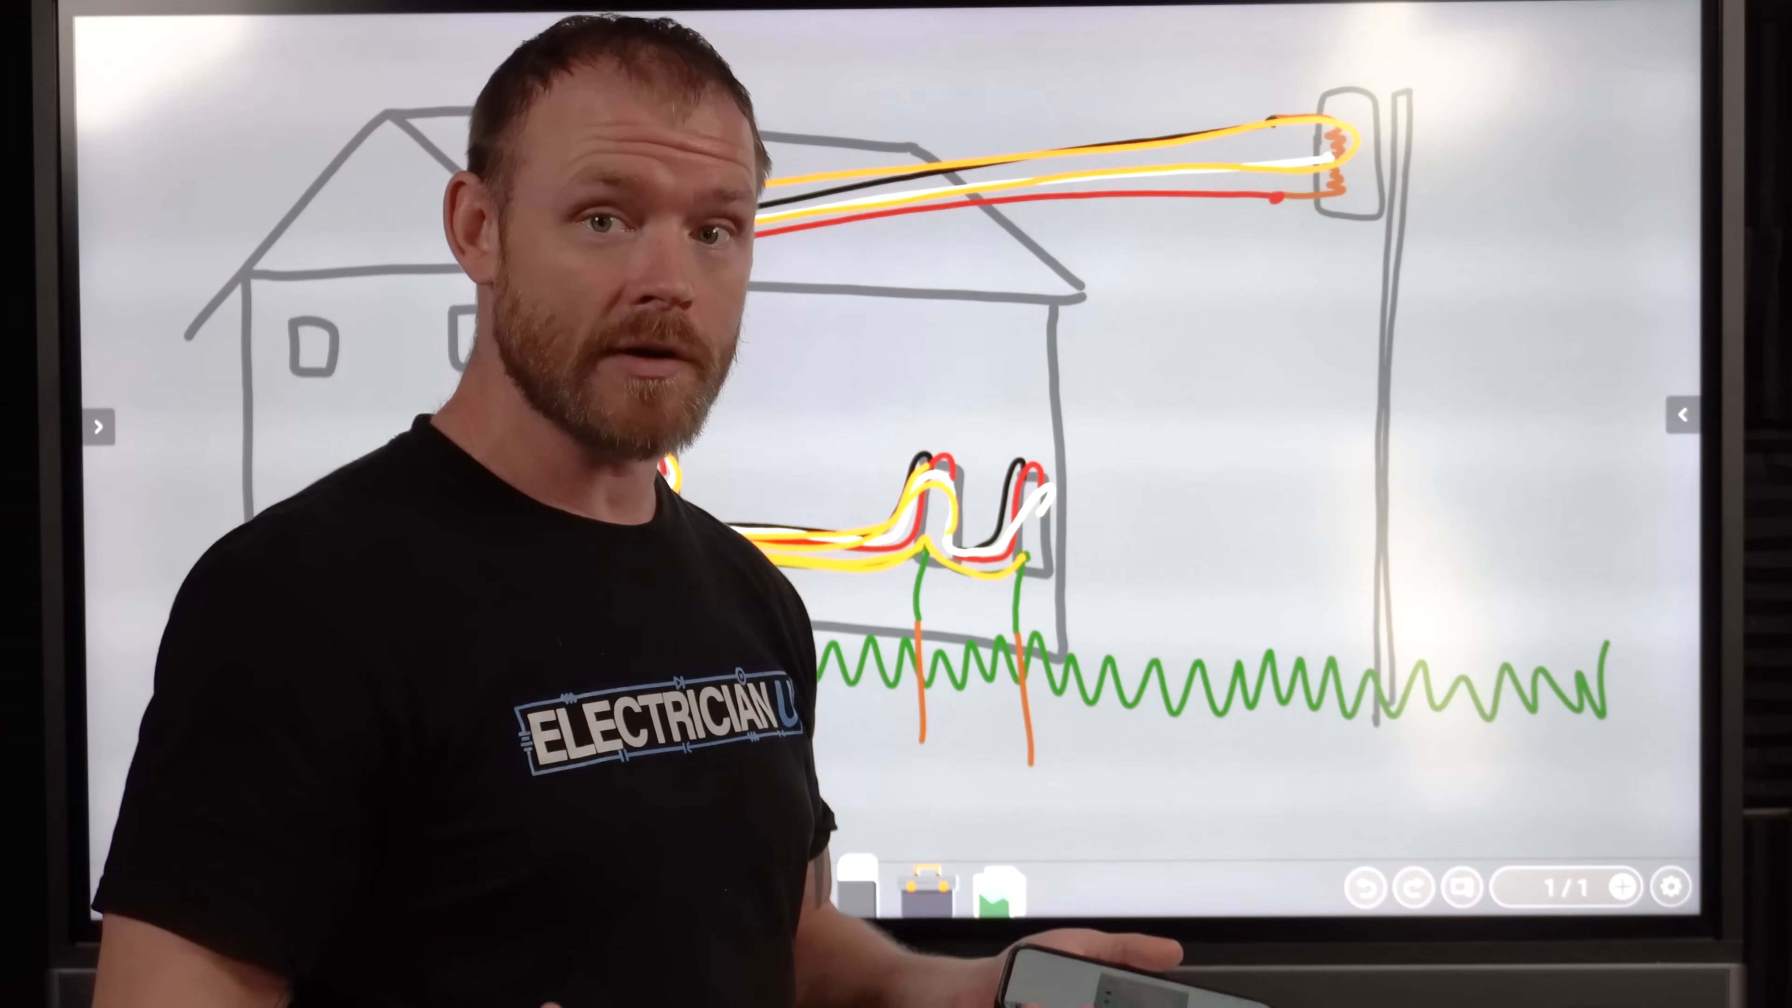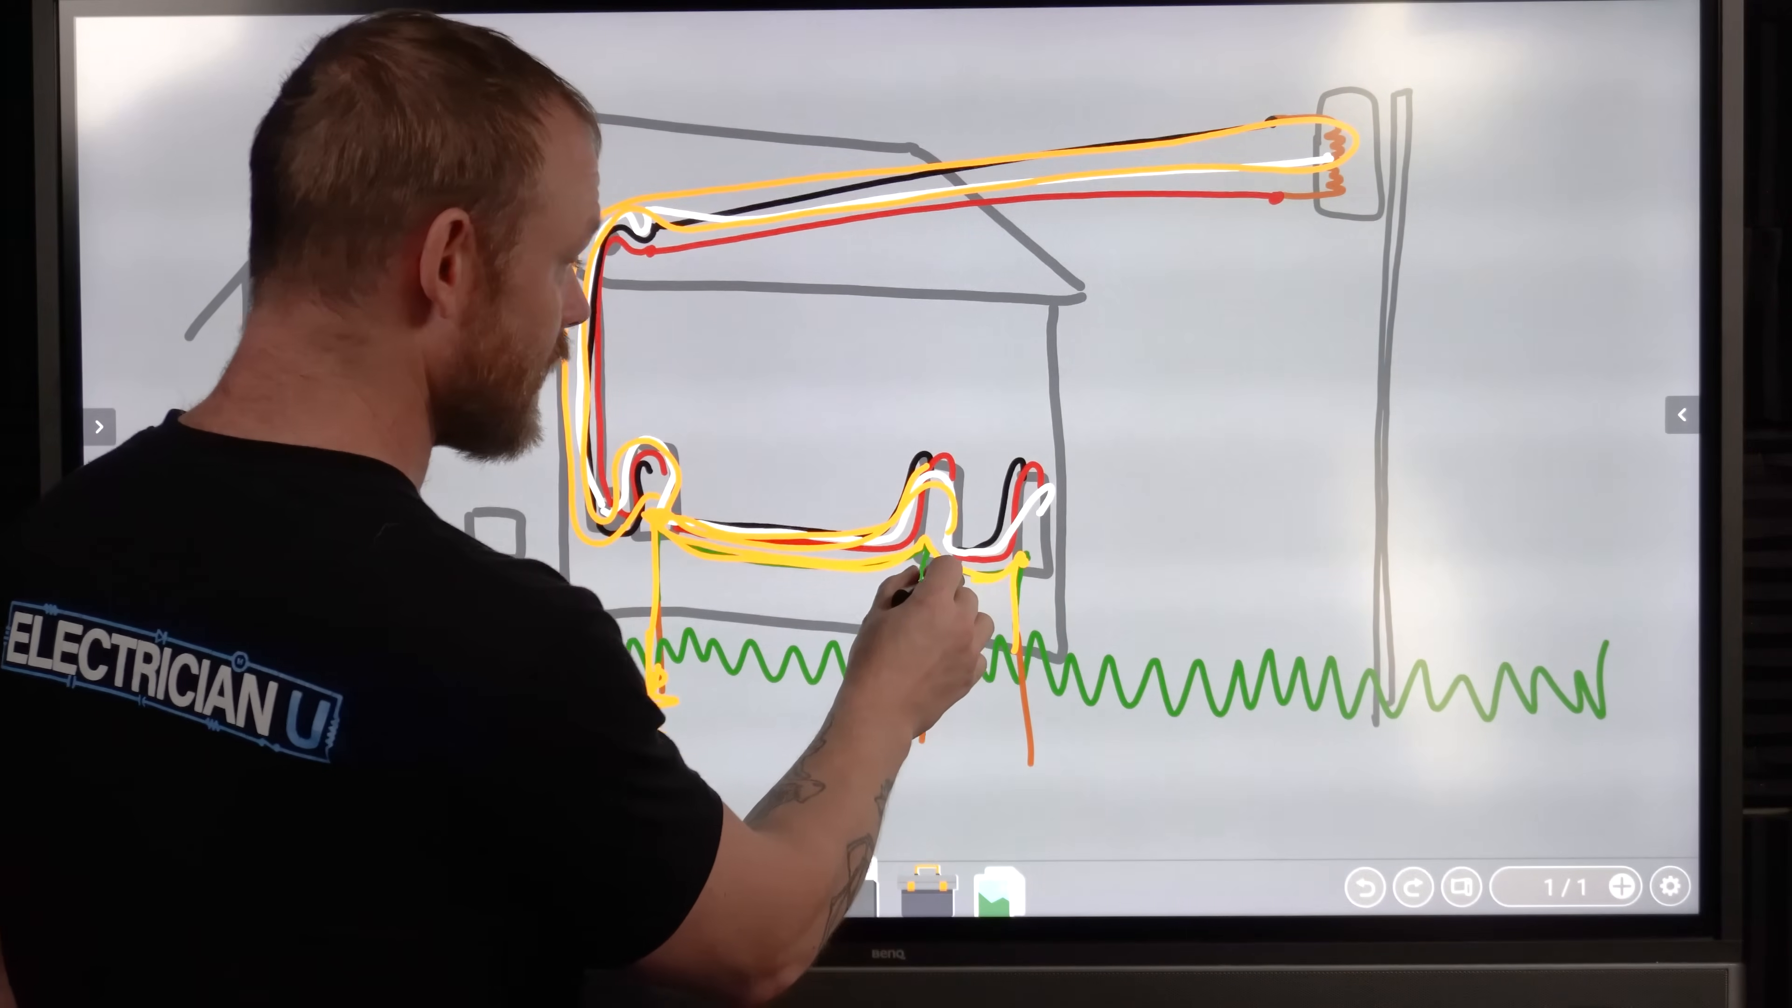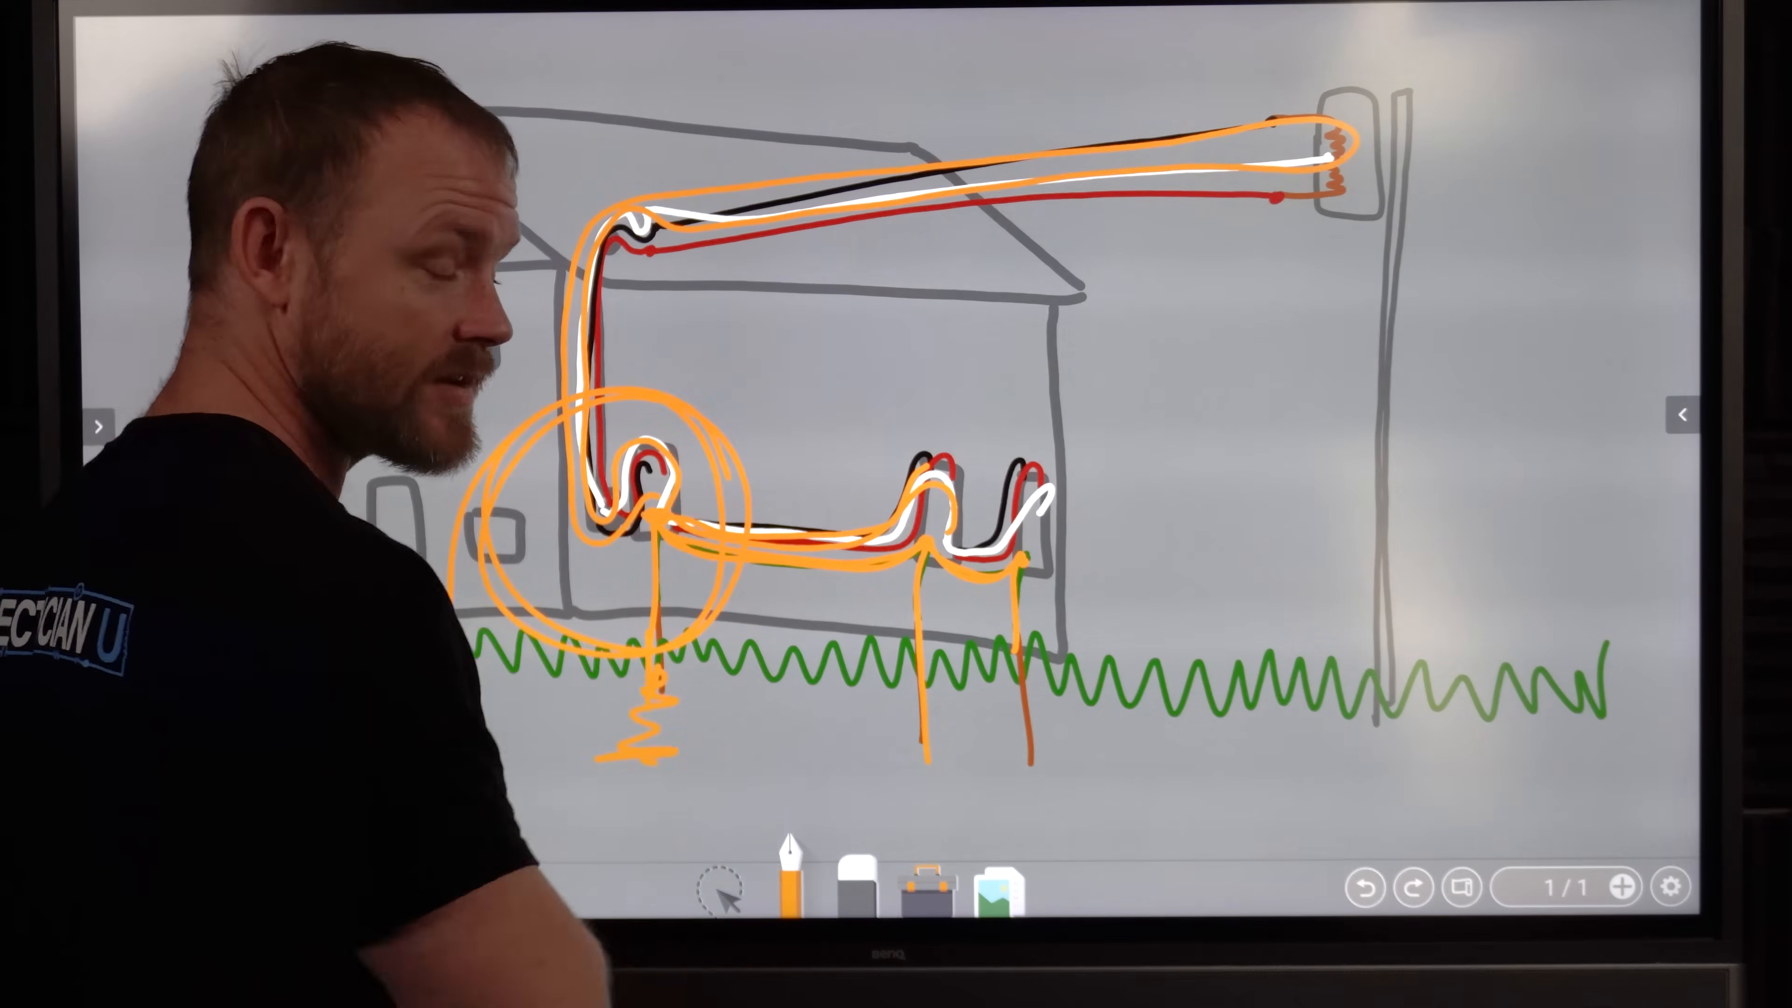So just make sure if you're going to have supplementary ground rods, which is allowed by code, however many of them you want, just don't connect them to neutral at any of the sub-panels. Just make sure each ground rod goes to the ground bus, has an equipment grounding conductor that goes to the next panel. You got an equipment grounding electrode conductor that goes down to the ground bar for the next one, that it's connected to the equipment grounding conductor. And the only place that you make a bond to neutral is still at the service.